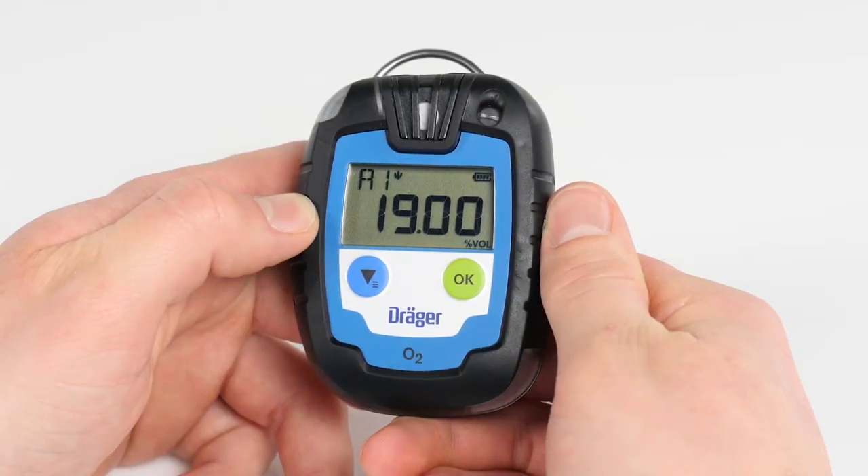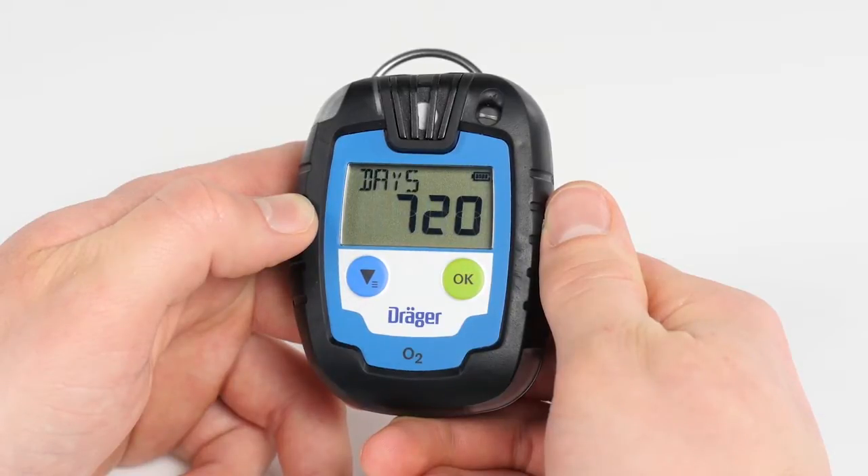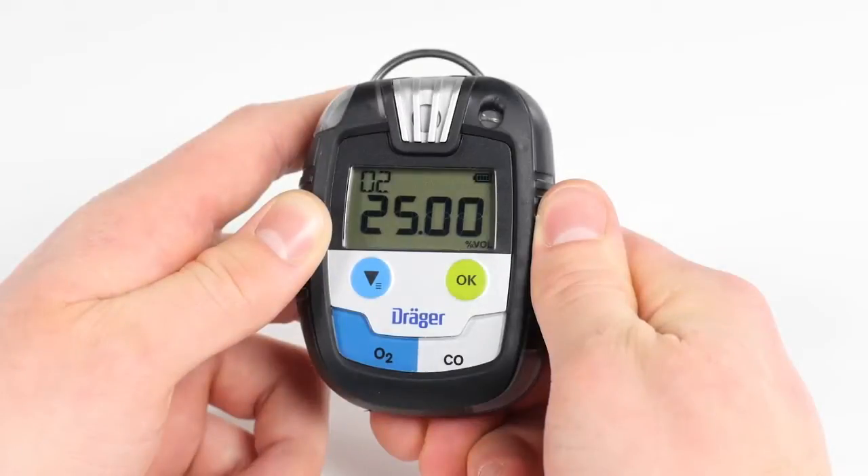Arrows display a rising or declining gas concentration. The remaining operating life in days is shown for the Pac 6000. If configured, the next due date for adjustment is also shown. The Pac 8500 indicates the gases and their relative alarm thresholds successively.